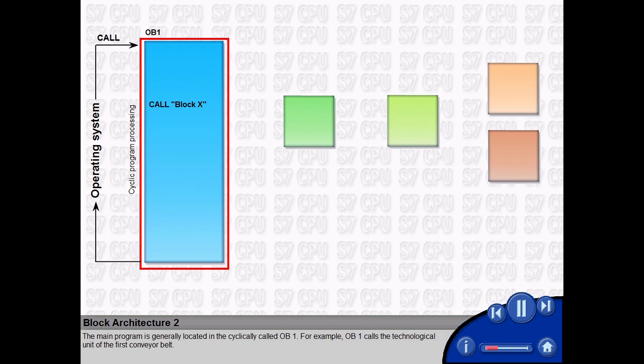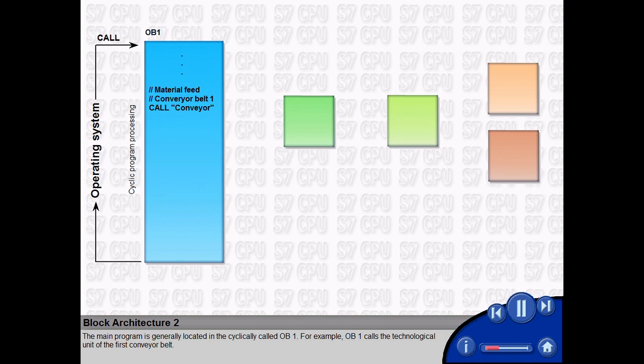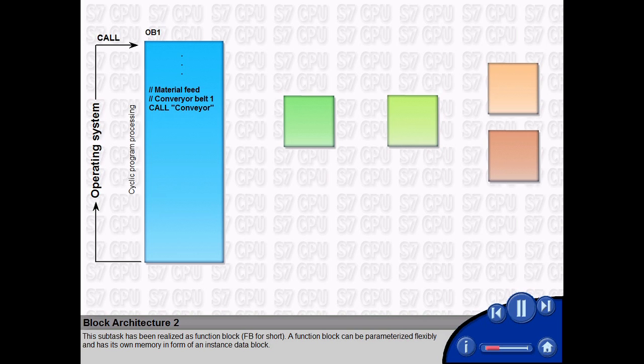For example, OB1 calls the technological unit of the first conveyor belt. This subtask has been realized as function block, FB for short. A function block can be parameterized flexibly and has its own memory in form of an instance data block.